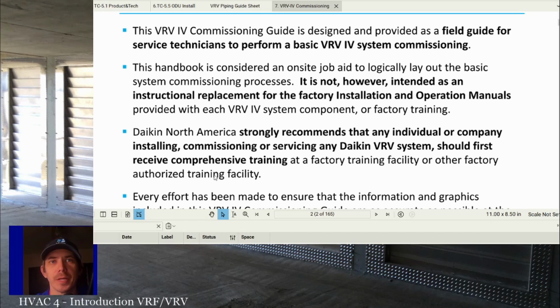Whatever the equipment manufacturer you're doing is, whether it's Daikin or Carrier or Mitsubishi or LG and so forth, you need to get training on that particular manufacturer's requirements before you do any installation of the equipment. If you have not been trained but you're helping on a job, then make sure you consult somebody who's had training before you do anything with the equipment, because every manufacturer has their quirks when it comes to VRF systems. And if you follow the rules from one manufacturer on another manufacturer's equipment, you may end up in a situation where it doesn't work properly.